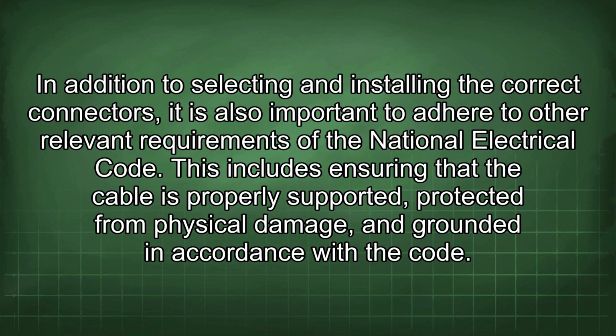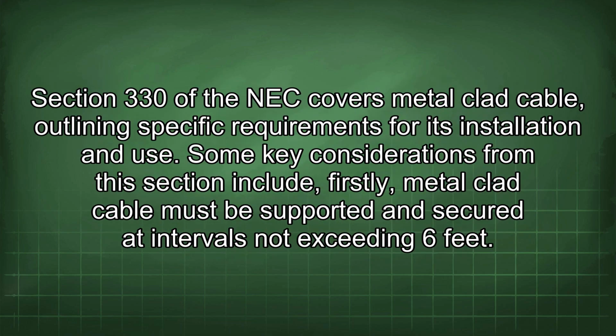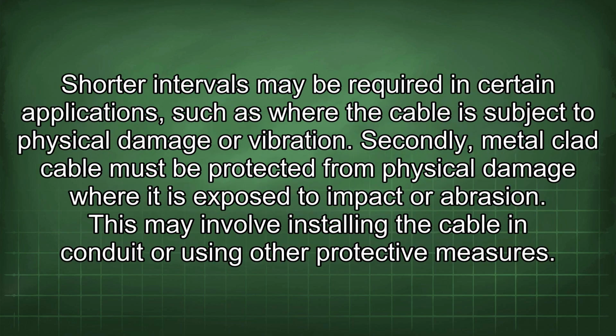In addition to selecting and installing the correct connectors, it is also important to adhere to other relevant requirements of the National Electrical Code. This includes ensuring that the cable is properly supported, protected from physical damage, and grounded in accordance with the code. Section 330 of the NEC covers metal-clad cable, outlining specific requirements for its installation and use. Some key considerations from this section include: firstly, metal-clad cable must be supported and secured at intervals not exceeding 6 feet. Shorter intervals may be required in certain applications, such as where the cable is subject to physical damage or vibration.